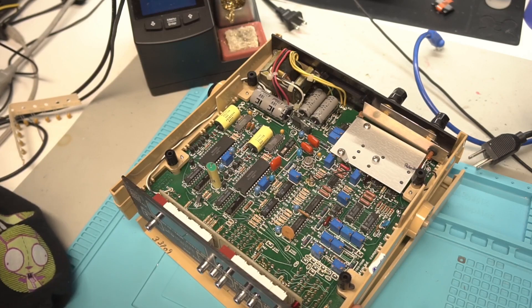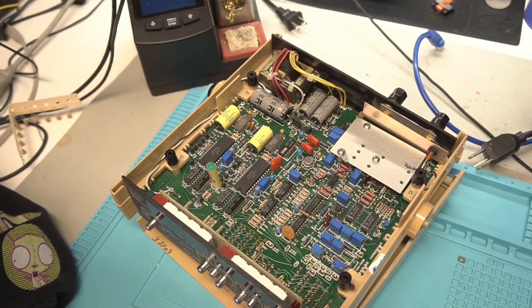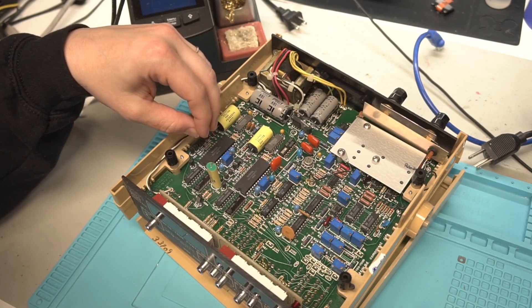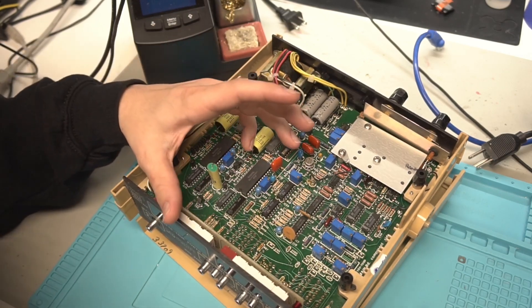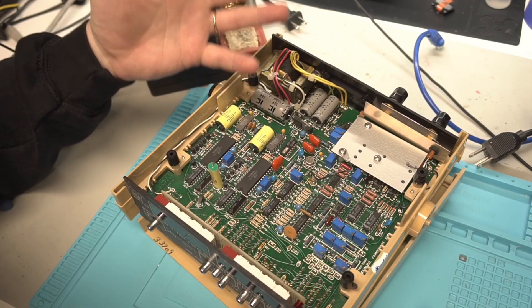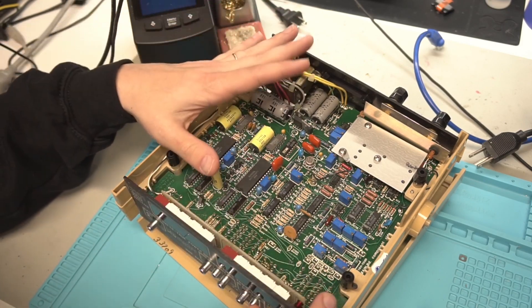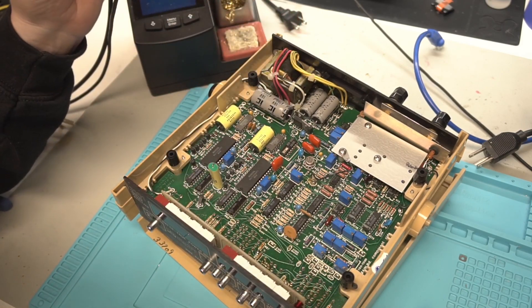So I got that one bad tantalum capacitor out. We're not going to replace the rest of them. But if this was an instrument that you plan to use a lot or were interested in keeping it, I would definitely replace all of them.